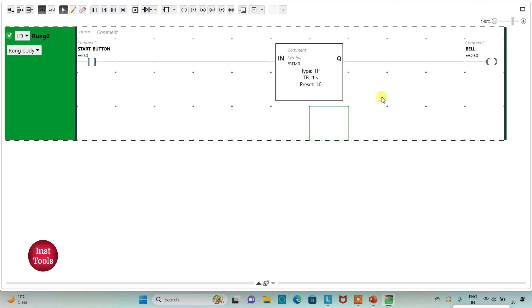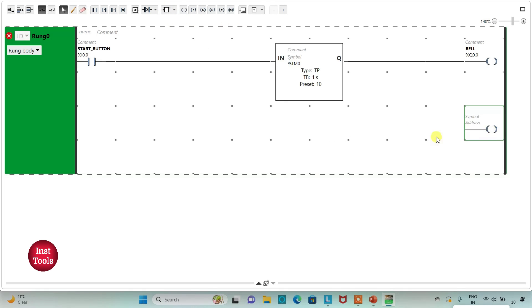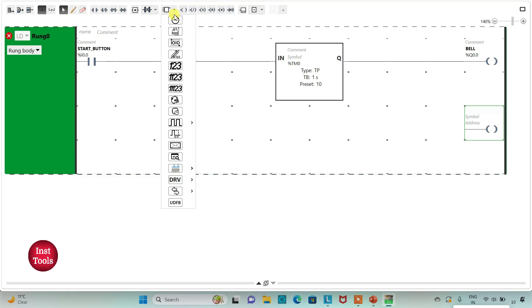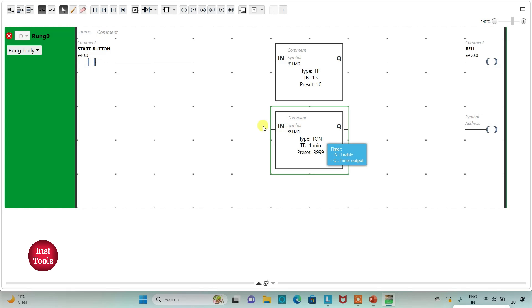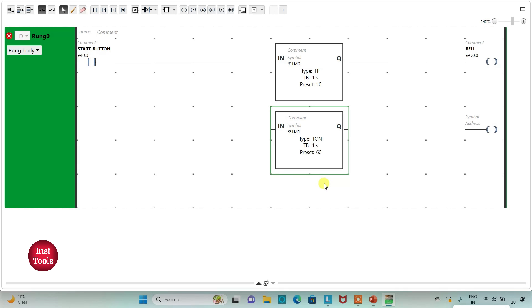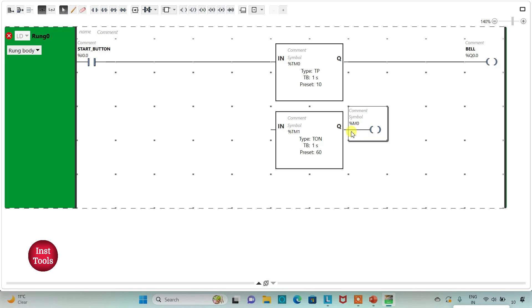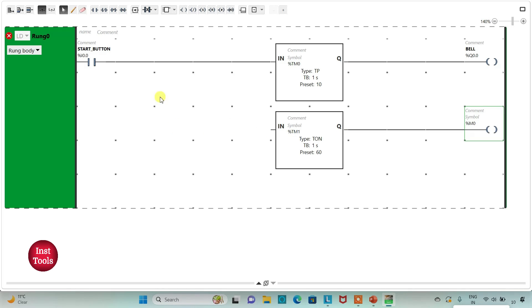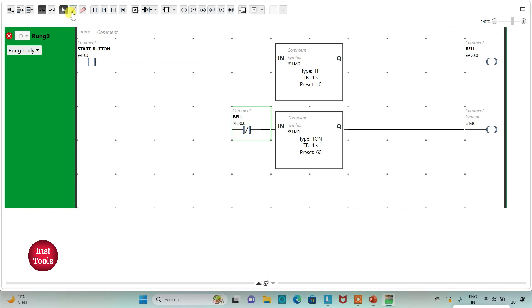There will be a delay of 1 minute for the bell to turn on again, so I will add a new rung with one more coil and a TON on-delay timer. I will change the time base to 1 second and the preset value to 60, then click Apply. I will assign the address M0 to this coil. Then I will insert a normally closed contact with address Q0.0, which is the bell, and connect it in the rung.